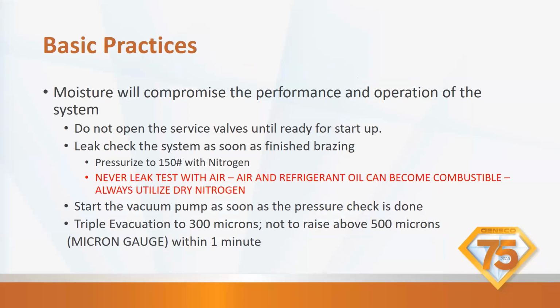Trane, American Standard, RunTru, Ameristar, all say pressurize to 150 pounds. You cannot pressurize it to 600 pounds like you would a mini split. Our valves will leak through over probably 350 psi. So if you stick with the 150, you're going to be better off. If it doesn't leak in a half an hour at 150, it's probably not going to leak at 300 either. Okay, so just remember, don't over pressurize it, because you can push nitrogen right through those valves, right into your refrigerant inside of your condenser. Okay, never test with air.